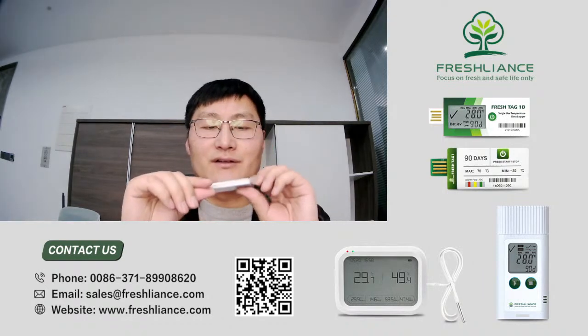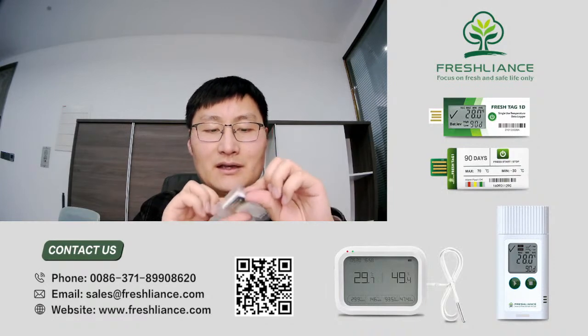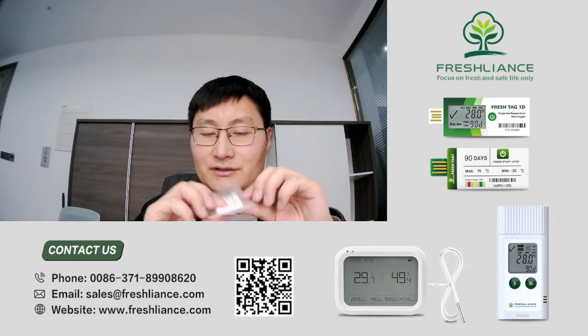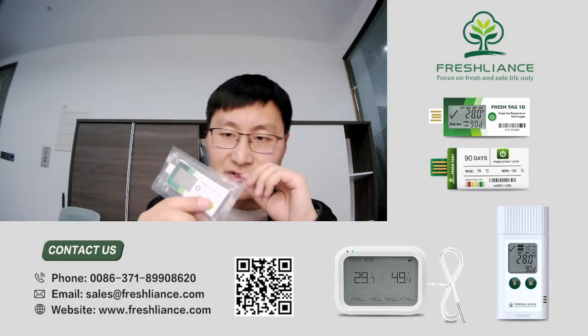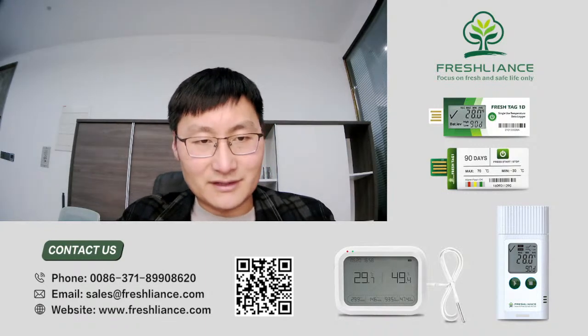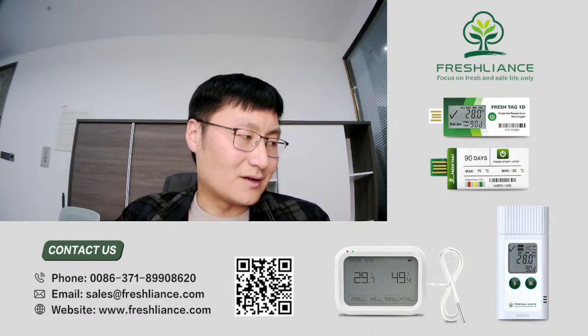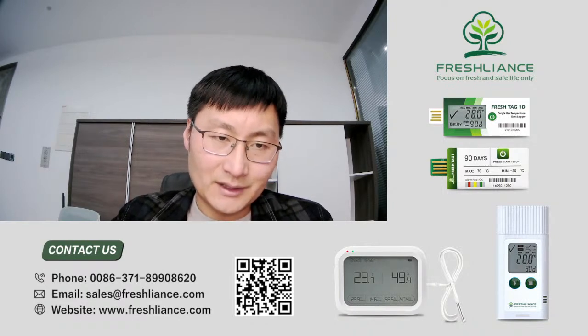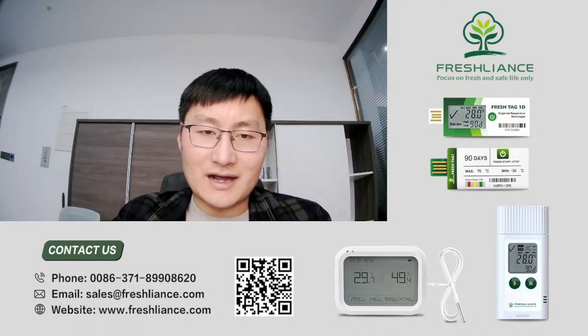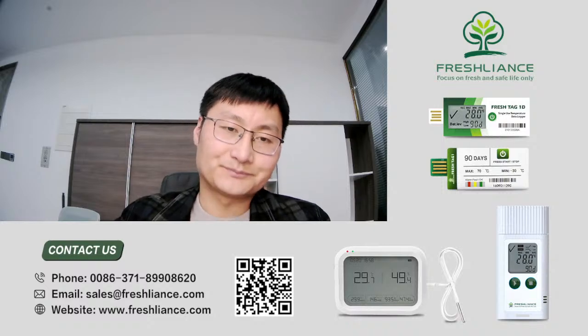This model, Fresh Tag 1D, is a single-use temperature data logger. So it monitors the temperature only. It has a temperature range of from -30 to 70 degrees. The temperature accuracy is ±0.5 degrees at full temperature range.